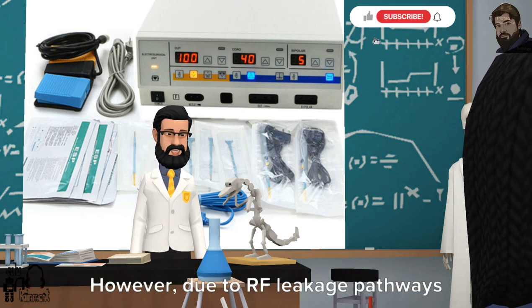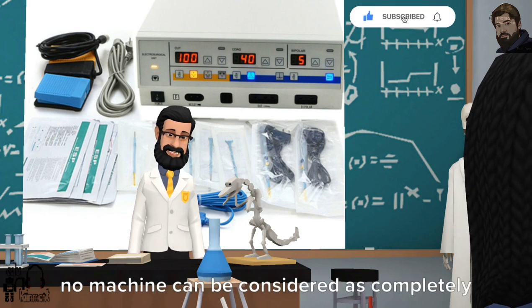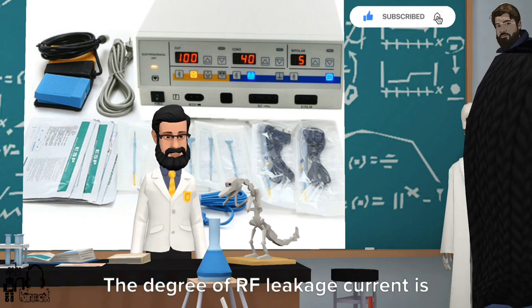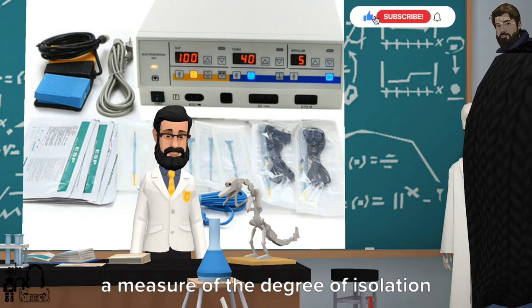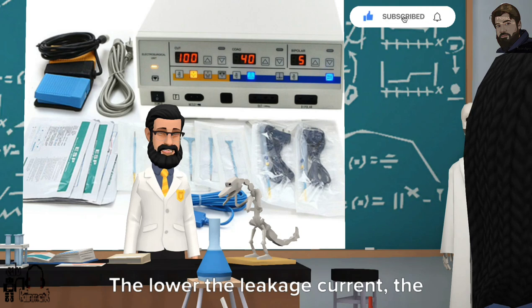The degree of RF leakage current is a measure of the degree of isolation of a particular machine. The lower the leakage current, the better the isolation.